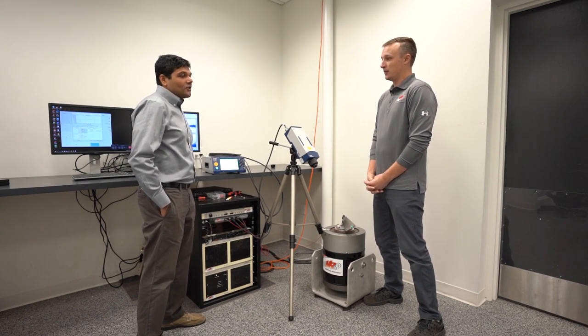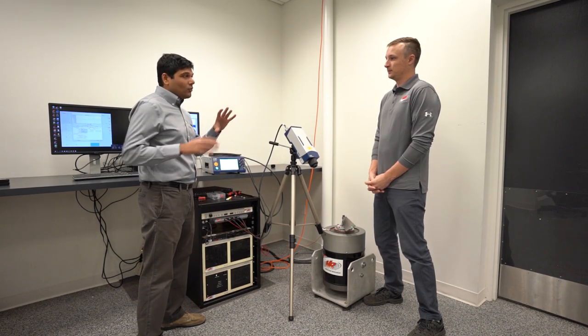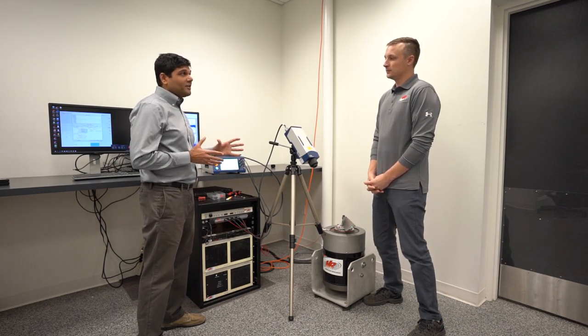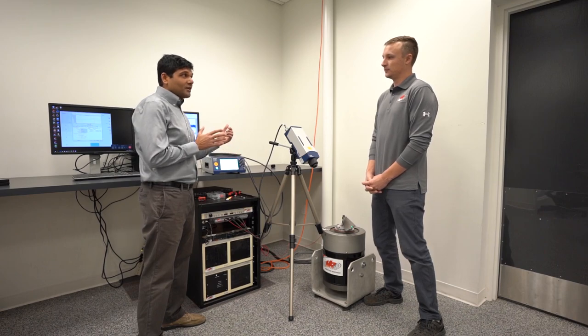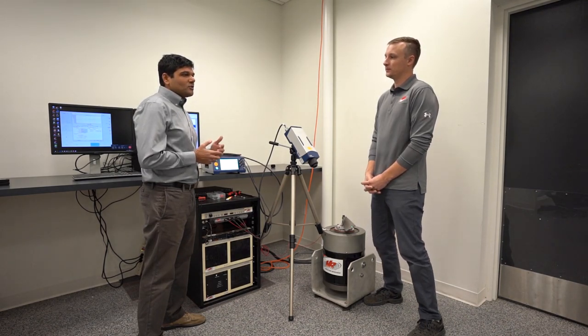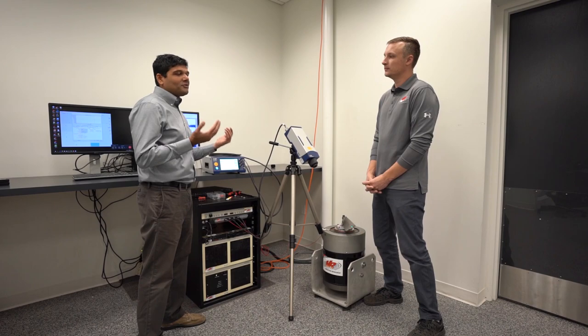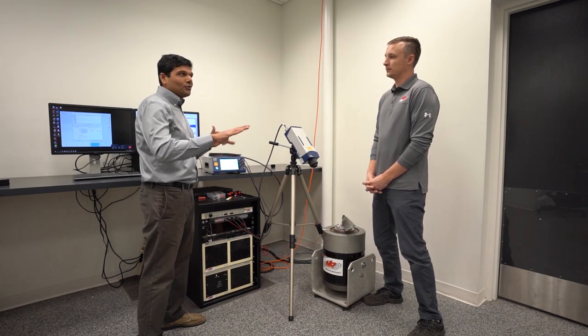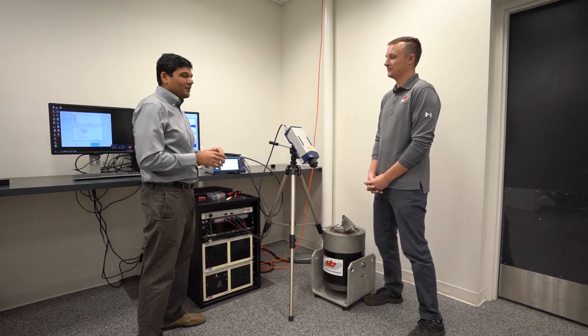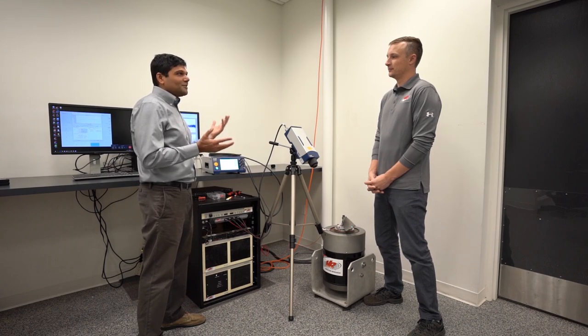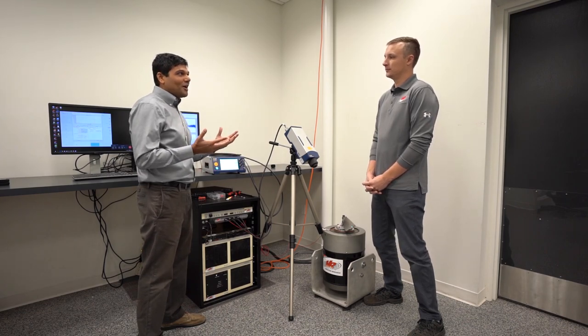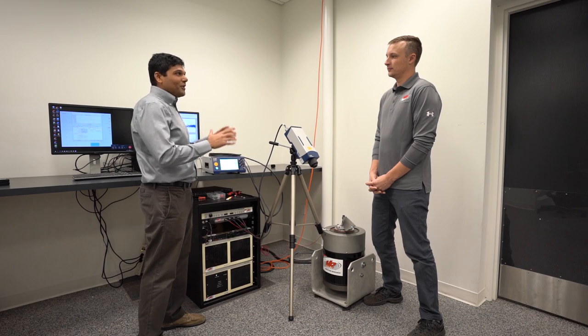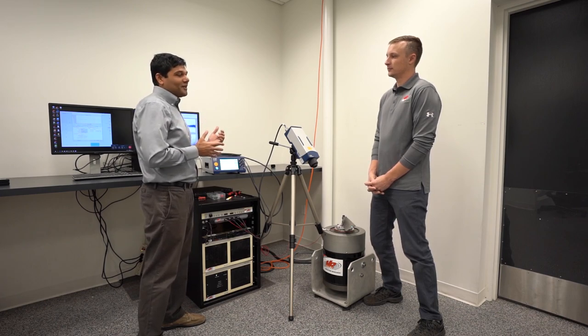So the rule of thumb is, generally speaking, the lower the frequencies of interest, you would choose direct displacement. Also, it depends on what quantity I'm after. If I'm after velocity, that's usually the go-to parameter to measure. And in most cases nowadays, the data acquisition systems are so smart that you can do everything you need to in your software.